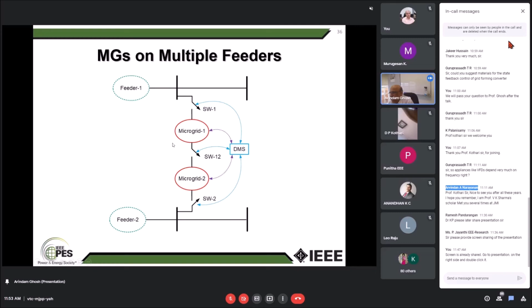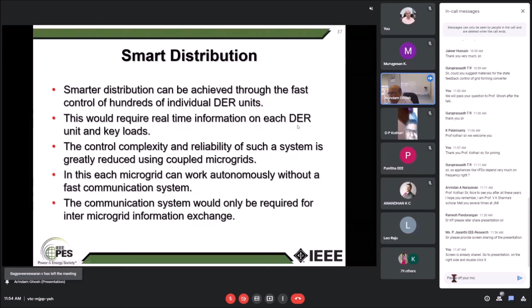So what is smart distribution? Smart distribution can be achieved through the fast control of hundreds of individual DER units. This requires real-time information on each DER unit and loads. Suppose you have the traditional system: central generation, transmission, substation, distribution network, and then you have a microgrid, all of them. But these microgrids are actually talking, only transferring power through what is called the power exchange highway. So the power exchange between the microgrid or the central generator or microgrids itself will go through this highway.